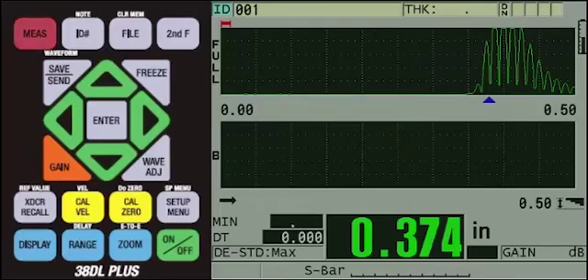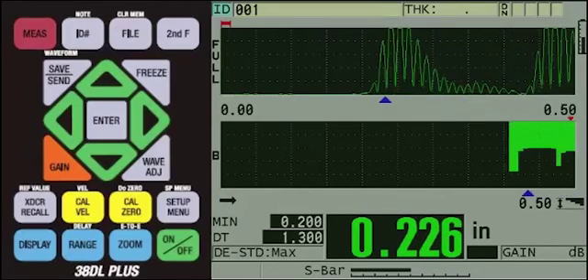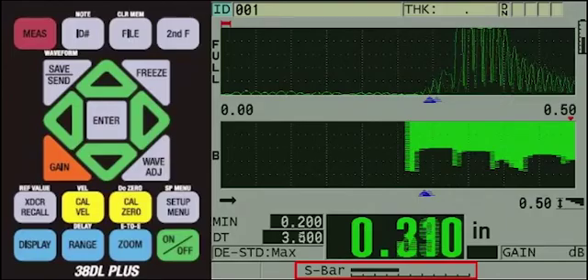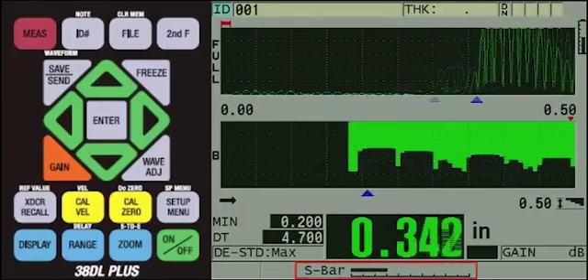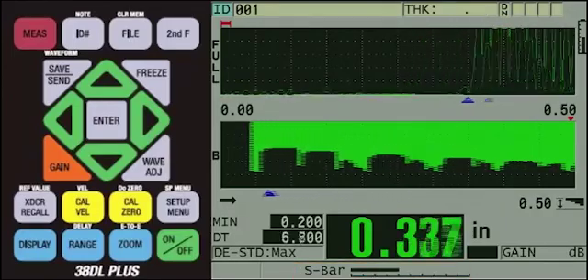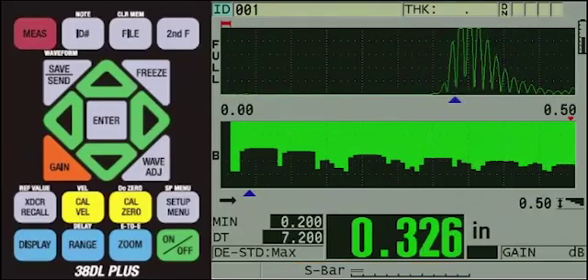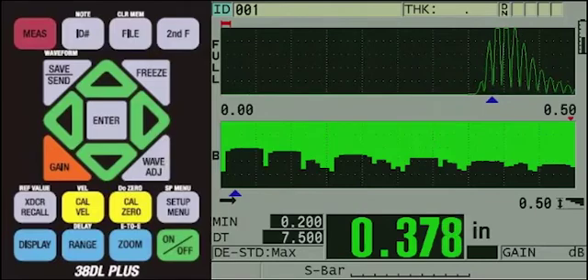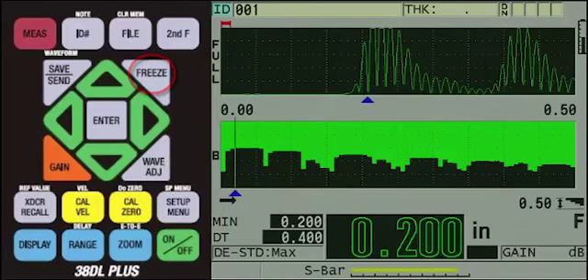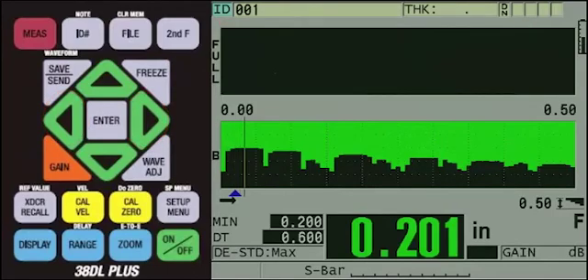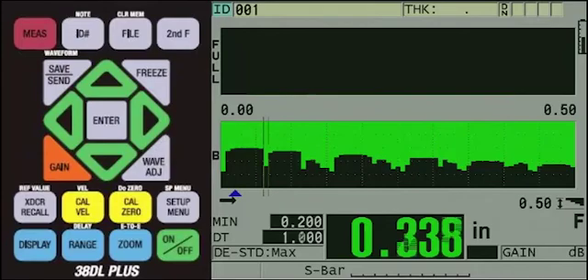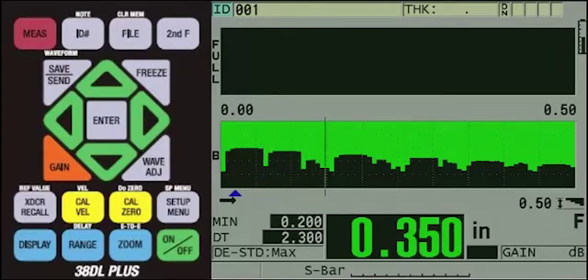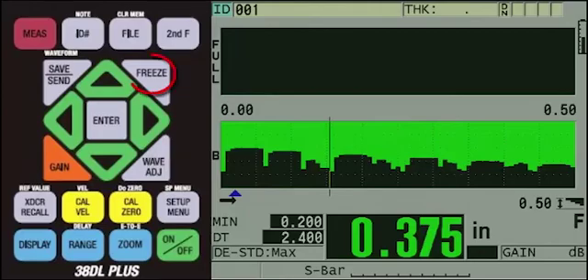Then, press the red Measure key to reset the captured minimum and the distance traveled. Then, you can begin scanning the plate. You can watch the speed bar at the bottom of the screen to make sure you do not move the buggy too fast. Since we have Freeze Review turned on, we can press the Freeze key at any point in the scan, and then use the left and right arrows to review different areas of the scan. The gauge displays the thickness in that spot and the distance the buggy has traveled to reach that spot. We can then press the Freeze key again, and continue scanning the plate.